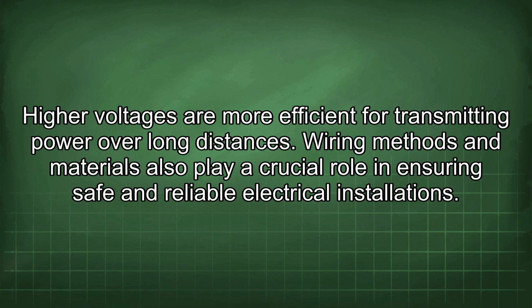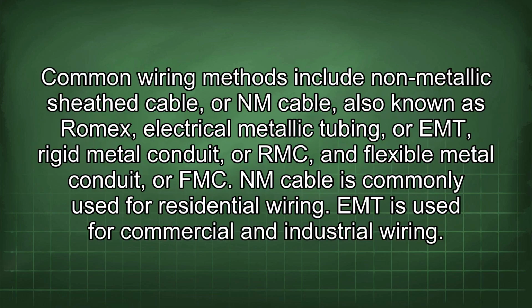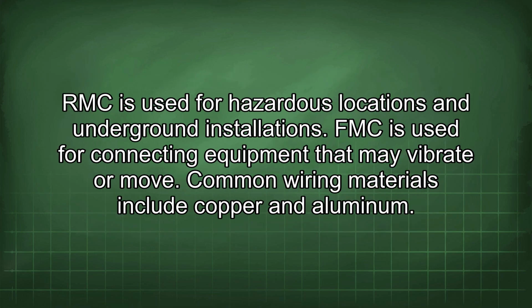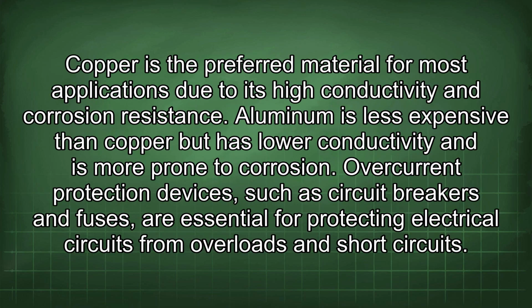Wiring methods and materials also play a crucial role in ensuring safe and reliable electrical installations. Common wiring methods include non-metallic sheath cable, or NM cable, also known as Romex, electrical metallic tubing, or EMT, rigid metal conduit, or RMC, and flexible metal conduit, or FMC. NM cable is commonly used for residential wiring. EMT is used for commercial and industrial wiring. RMC is used for hazardous locations and underground installations. FMC is used for connecting equipment that may vibrate or move. Common wiring materials include copper and aluminum. Copper is the preferred material for most applications due to its high conductivity and corrosion resistance. Aluminum is less expensive than copper but has lower conductivity and is more prone to corrosion.